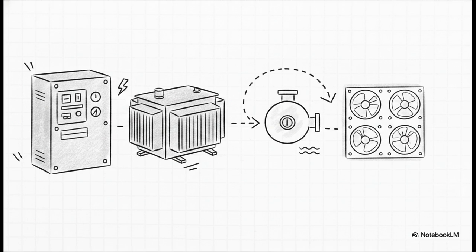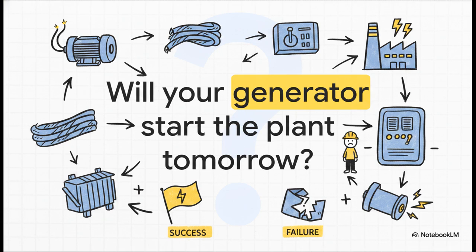Sometimes engineers do this by relying on the future addition of cooling fans to unlock that extra capacity when the demand eventually grows. Which brings us to the ultimate question I want to leave you with today. We've just seen how a simple 10% roll on one single pump ripples through the cables, the switchboards, the transformers, and right up to the main power generation. It all starts with those margins.